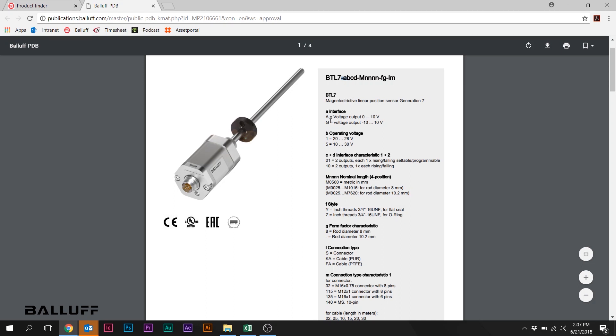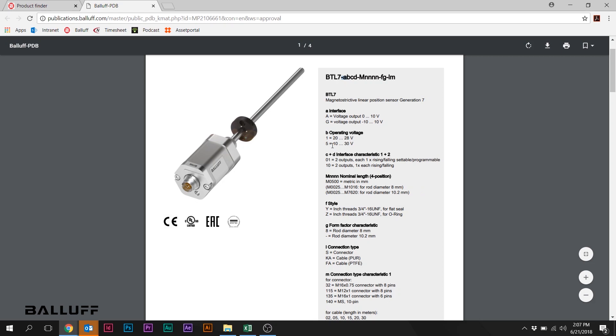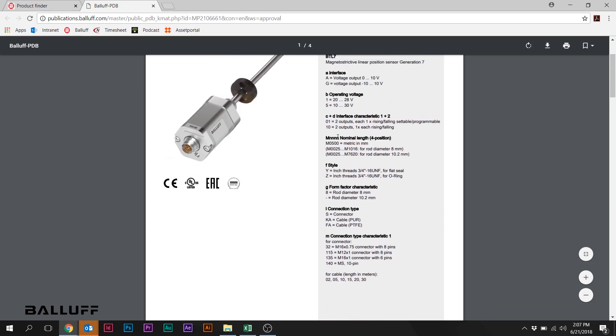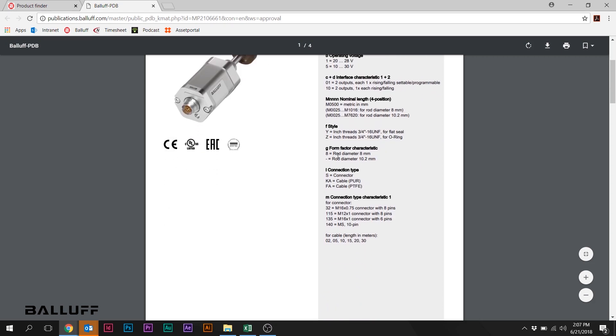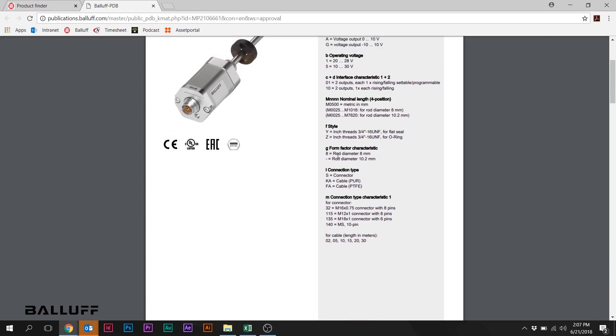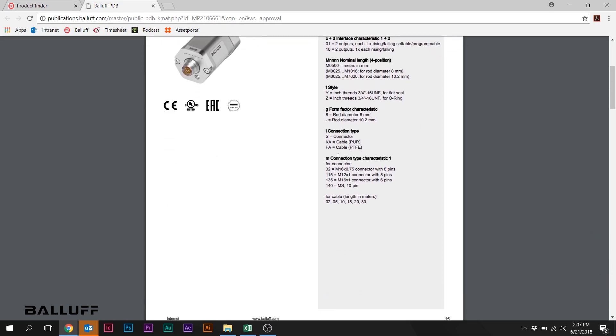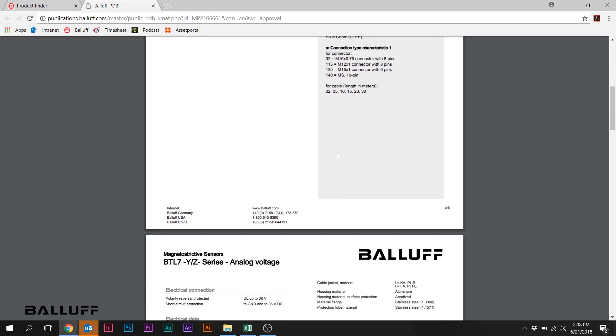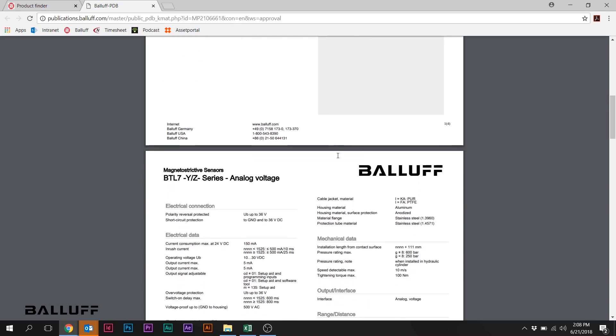So each of these lowercase letters here in the part number or type code are explained below. Lowercase A, for example, is the interface. We picked an A in our example, so that's a voltage output 0 to 10 volts. You can see the rest of the options listed below. So everything is explained here on the data sheet, so this is also a good reference tool to explain the Balluff part numbering breakdown and how it works.